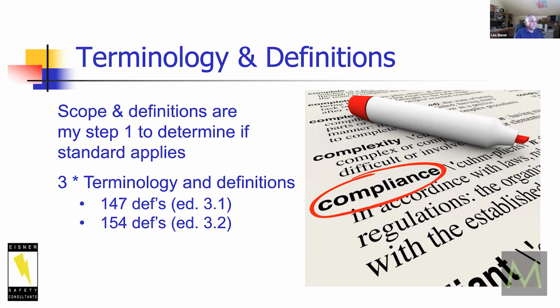I've sort of laughed at some of what regulators say the product is. Now FDA is saying for IVD equipment, the B and C standards that need to apply include 60601-1-2, the EMC for medical electrical equipment, which is not the standard that the scope would say. Totally not. There are IVD EMC standards, but FDA is not agreeing with that. Period. The end. That's an excellent example, but neither here nor there.